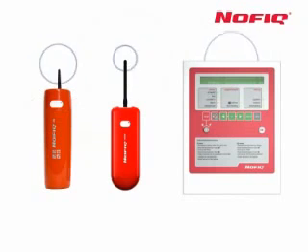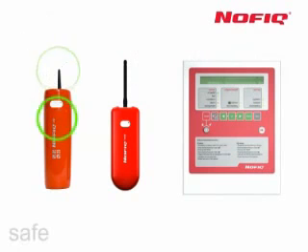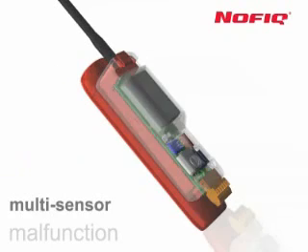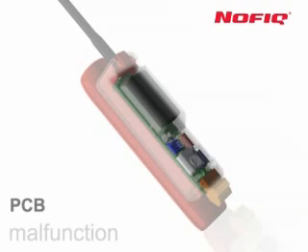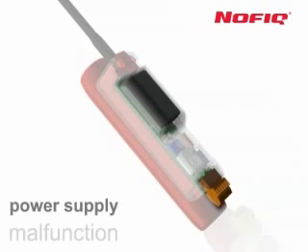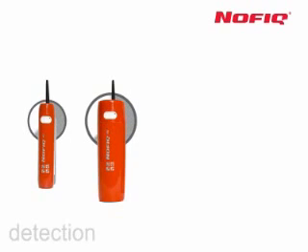The NOFIQ network conducts a self-check every 5 minutes by sending out a so-called heartbeat. If no errors are detected, the system is in safe mode. In the event of an error message, the unit shows exactly where that error has occurred — in the sensors, on the PCB, in the wireless network, or in the power supply due to low battery power or failure of the grid connection.